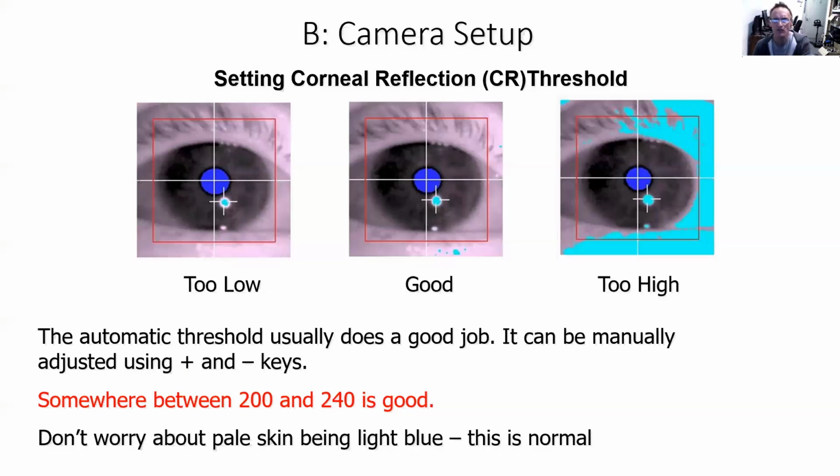If you've got 500 pixels in your corneal reflection and 5,000 in your pupil, then if any of those pixels change sample to sample, it's not going to change the average. In other words, the center, which is what the eye tracker is computing. And that's what gives you this nice, stable, clean data. So if you're seeing noise, you're seeing shaky gaze cursors, whack up your pupil threshold with the up arrow, lower your corneal reflection threshold with the minus key, and you'll probably find it gets better.